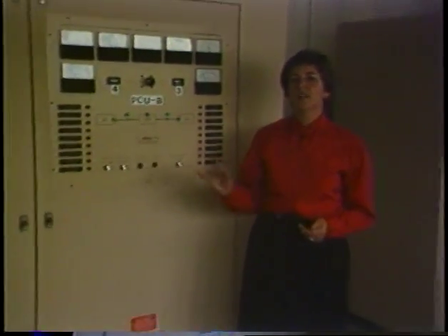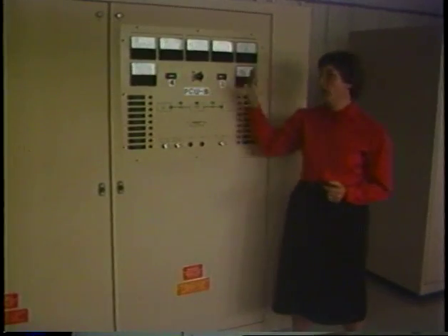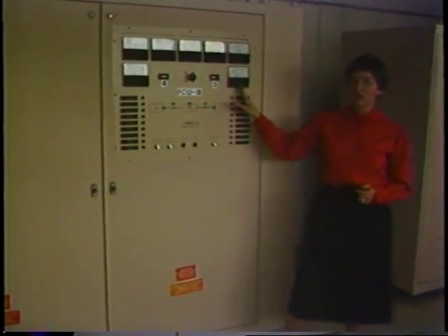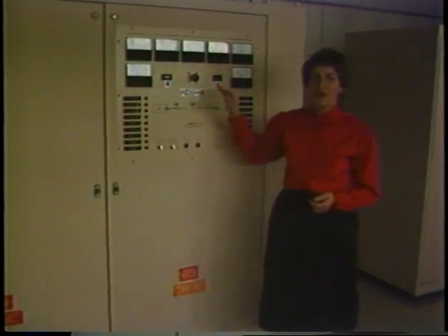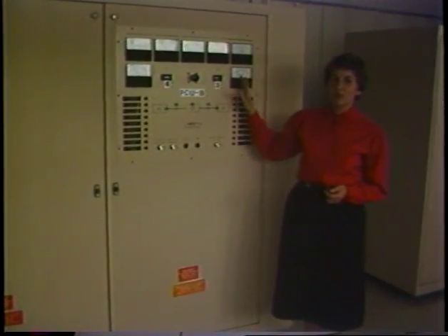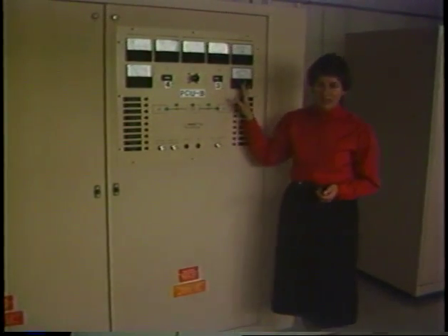This power conversion unit takes care of all the power that's coming out of the B field presently and converting it from DC form to AC, where it goes into the high school. So the B field at present is producing 20 kilowatts of power and pushing out into the high school in AC form about 17 kilowatts.